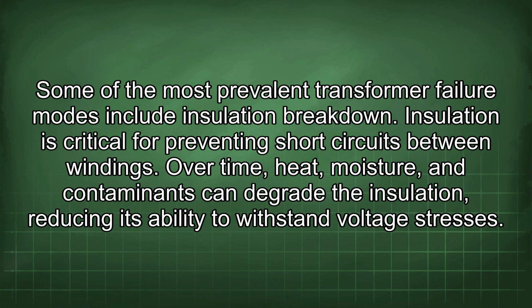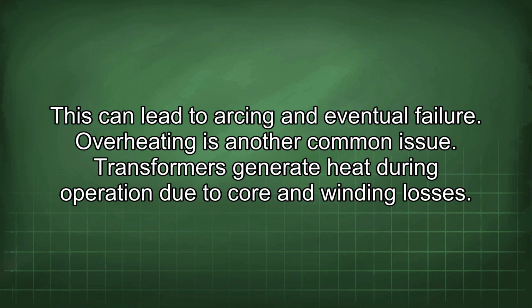Insulation is critical for preventing short circuits between windings. Over time, heat, moisture, and contaminants can degrade the insulation, reducing its ability to withstand voltage stresses. This can lead to arcing and eventual failure.